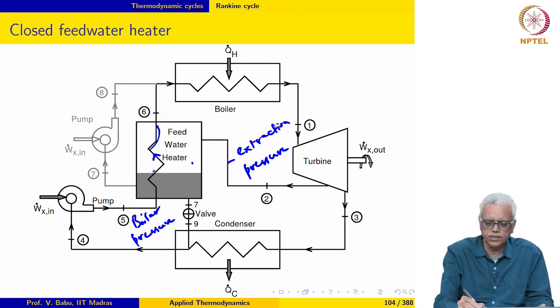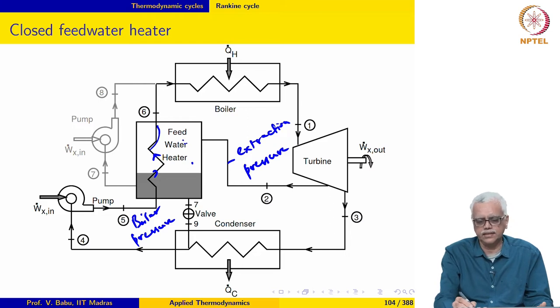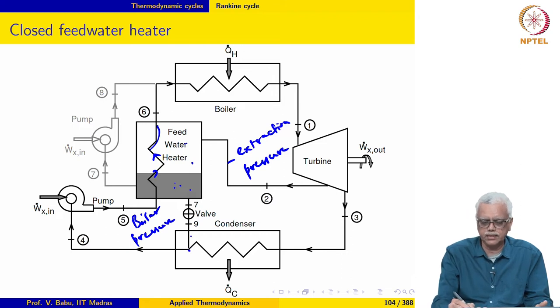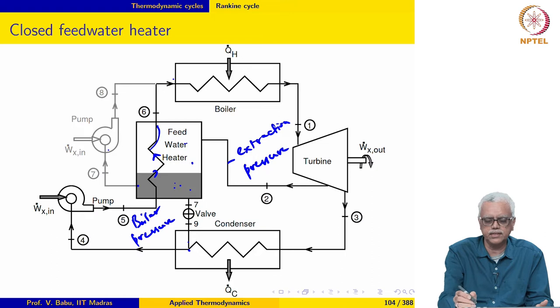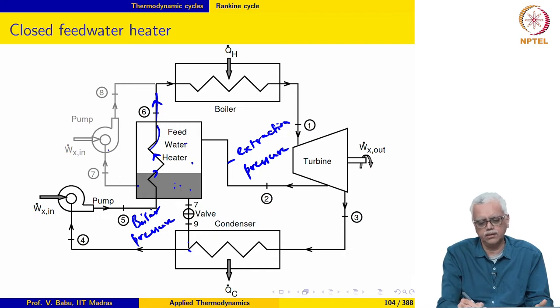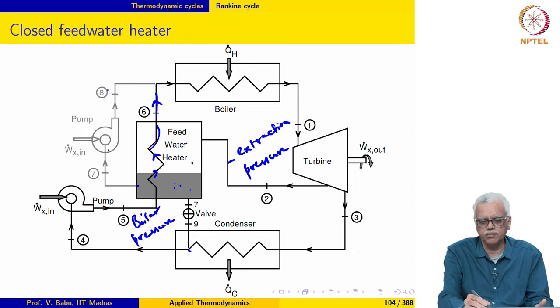The feed water, as it moves through the heater, is heated by the steam that enters. As the steam transfers its enthalpy to the feed water, it condenses and there is a condensate or saturated liquid at the bottom of the feed water heater. There are two strategies for handling this saturated liquid condensate: one is to throttle it to the condenser pressure and send it to the condenser, or pump the condensate using a pump to the boiler pressure and send it to the boiler along with the feed water exiting the heater.